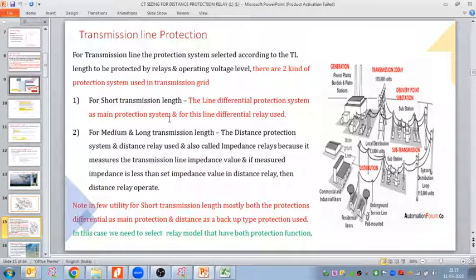If my transmission line is short, when I say short length it means around 5 kilometer, 10 kilometer. The CEA says a length less than 30 kilometer we can call a short transmission line. For a short transmission line we go with the line differential protection system, so we select the relay that has the line differential protection function. If the transmission line length is medium or long, then we need to select the distance protection relay. This we discussed yesterday.